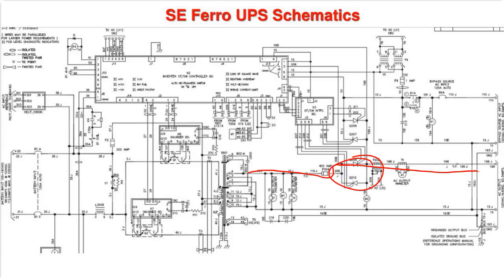Okay, if you're going to do work, basically what UL says is if you're going to do work on here and you want to de-energize this back at your MCC, UL says you have to have something that, if we have a short circuit here, so that becomes connected to that through a short circuit, then we need a circuit that says, okay, if somebody has deliberately switched off the bypass here, that de-energizes this coil here and opens up these contacts. And therefore, we can't backfeed the circuit this way when somebody has deliberately switched off the bypass AC input breaker.